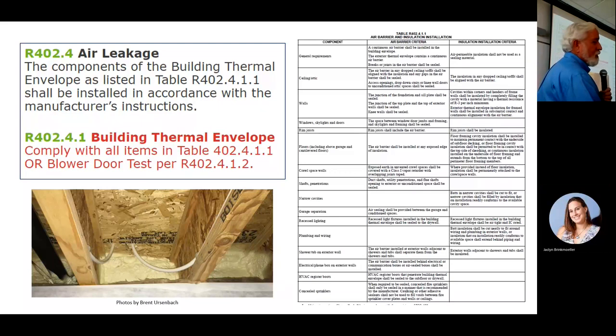What a blower door test is basically is that we pressurize or depressurize the house, simulating wind on all sides of the house, and see how much it leaks. We just measure how much air it takes to maintain a certain pressure. Kind of an analogy that I like to use is, have you ever had a hole in a tire and you put your air compressor on it and you can hold the tire up as long as you keep the compressor on it, right? Well, we take a house and we take it to 50 pascals, which is 0.2 inches of water column, which isn't very much pressure.